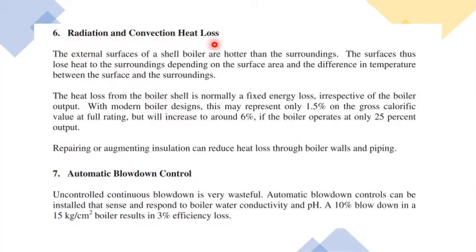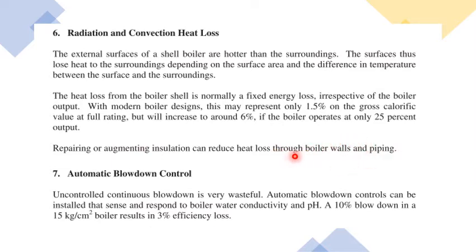The sixth point is radiation and convection heat loss. If the boiler body insulation or any component is not properly insulated, this leads to radiation and convection heat losses. These must be addressed promptly. Repairing or augmenting insulation can reduce heat loss through boiler walls and piping, leading to better boiler efficiency.